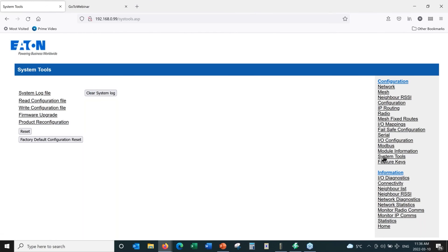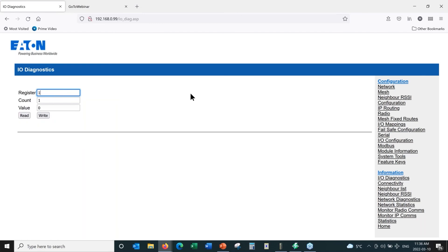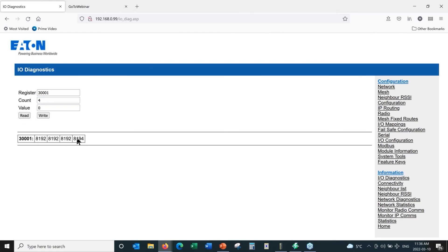A couple of different parameters are all under System Tools. The I/O Diagnostics is a repeat of the same menu seen earlier. For example, to look at analog inputs 1 through 4 — that's registers 30001 and onward — I can click Read, and I can see 8192, which is the factory zero value representing zero milliamps. So 8192 in raw counts equals zero milliamps. I can also write values to these radios and turn on and off the digital outputs if desired.